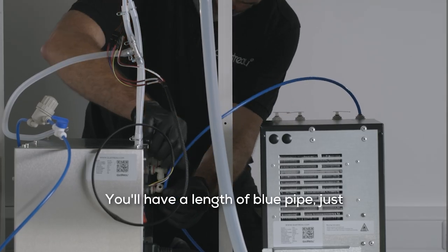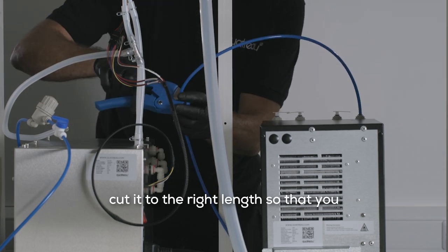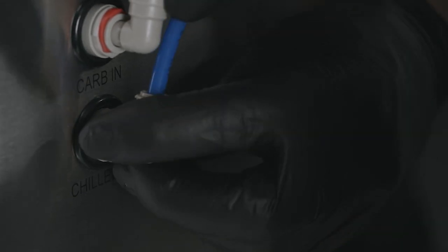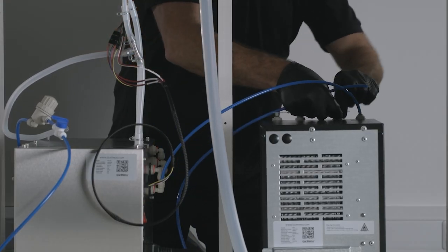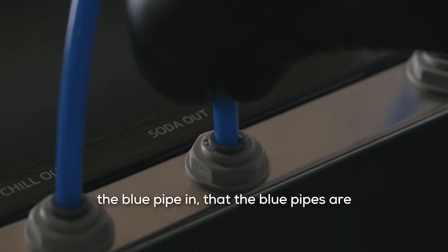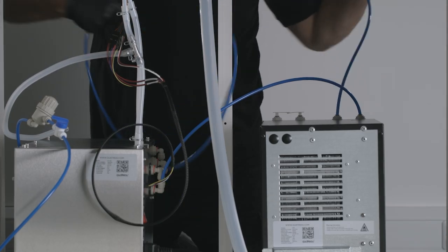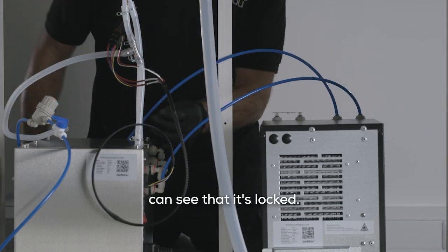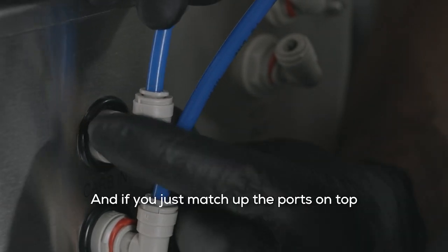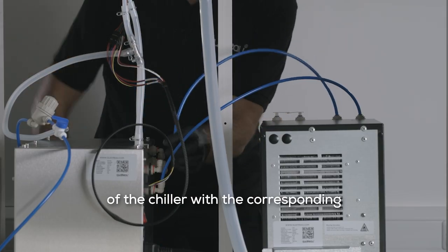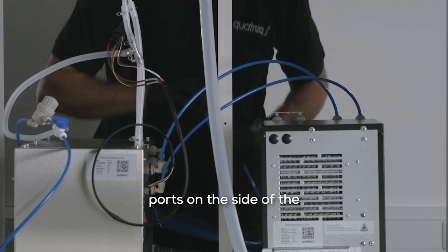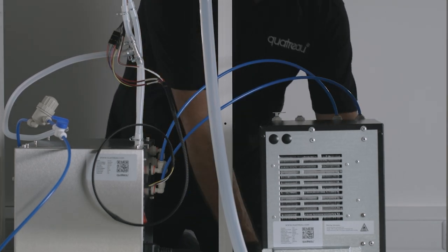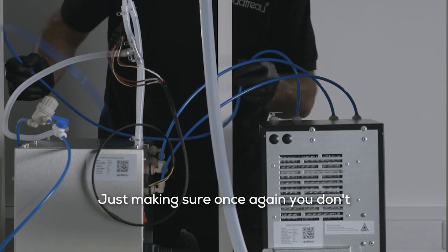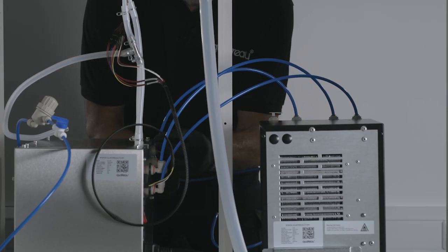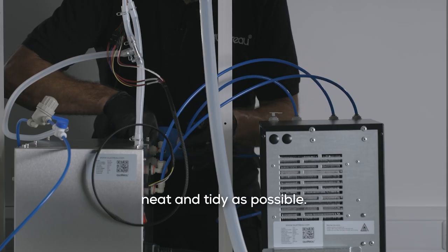You'll have a length of blue pipe. Just cut it to the right length so that you don't have too much excess of pipe. Try and keep it as neat and tidy as you possibly can. Once again, making sure that when you push the blue pipe in, the blue pipes are locked into the push fittings and that the collar comes out when you pull it so that you can see that it's locked. And if you just match up the ports on top of the chiller with the corresponding ports on the side of the water heater control unit. Just making sure, once again, you don't have too much excess blue pipe. Just to try and keep it as neat and tidy as possible.